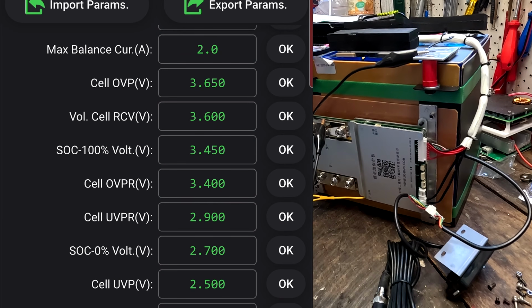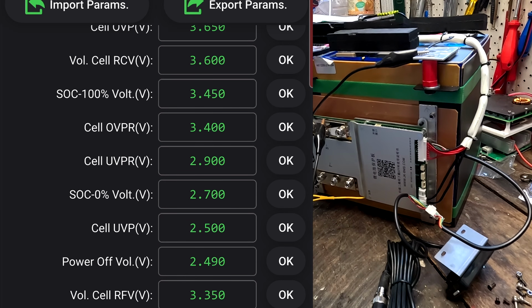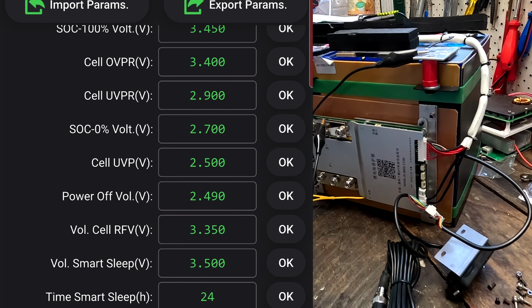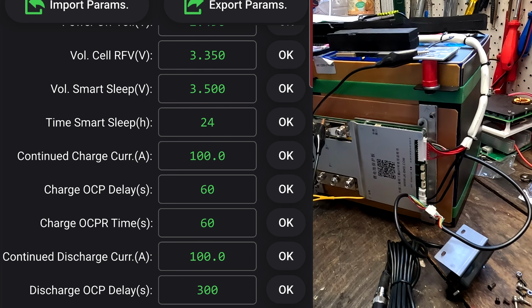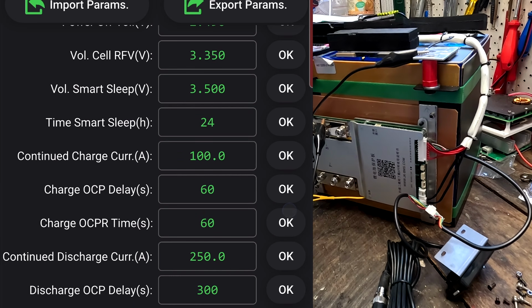The undervoltage recovery state of charge 0 is at 2.7, undervoltage protection 2.5, and turn off at 2.49. Continuous charge current 100 amps, that's fine. Continuous discharge current, okay, we need to go higher here. We set this one to 250 amps.